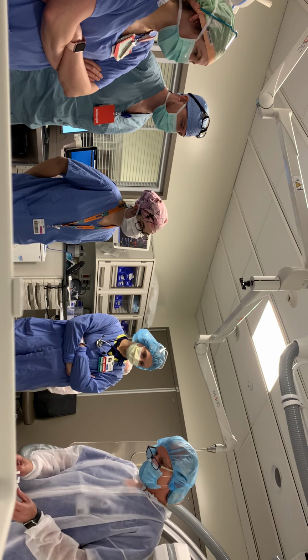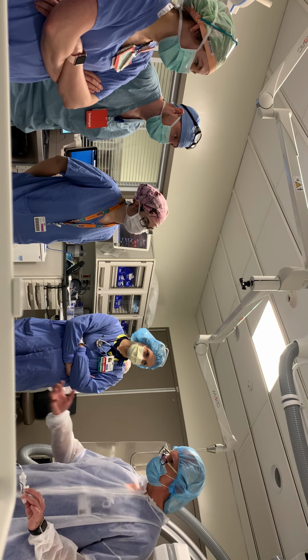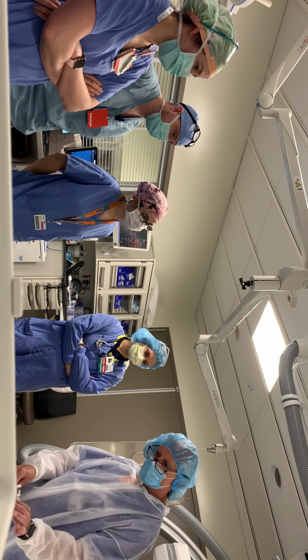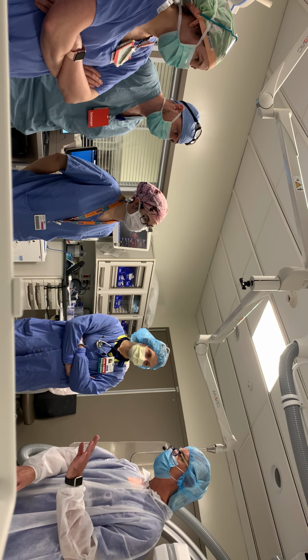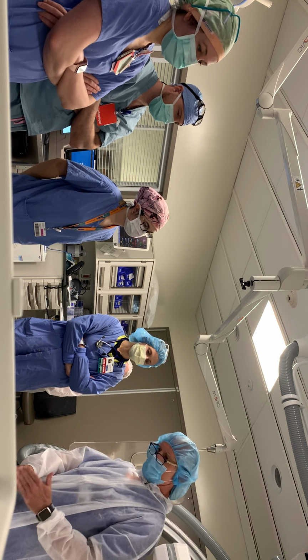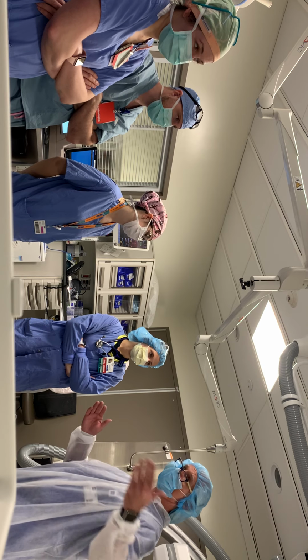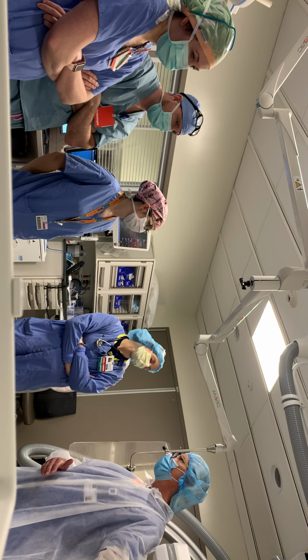A couple other things that I'll point out. This compensator line is there for counterbalance weight. If you have a little bubble in this line, don't waste two seconds on it. As long as the line is generally filled with fluid, you're good to go. This line, unlike a normal pole-mounted transducer, is not transmitting any pressure waveform. So a little bubble is not going to dampen anything.